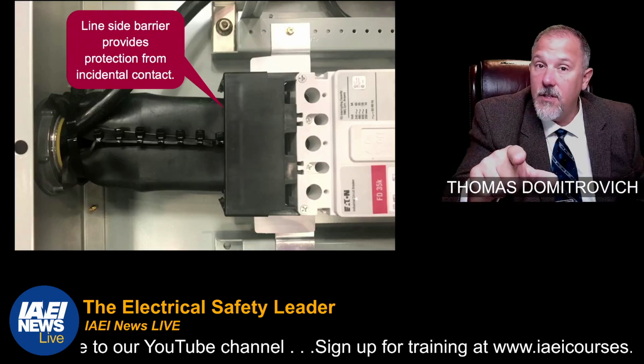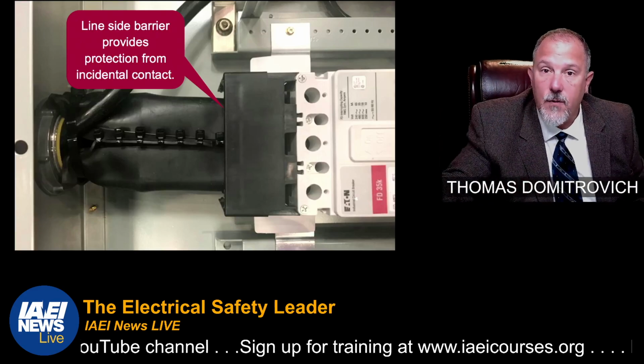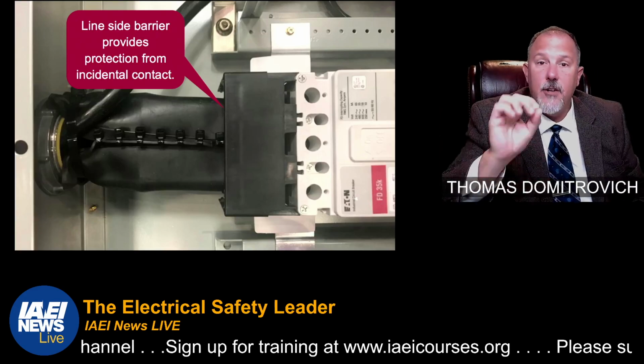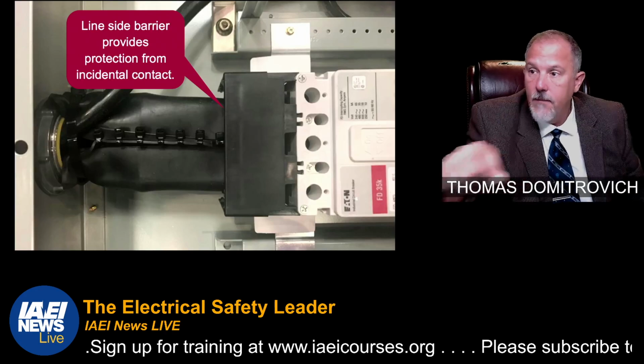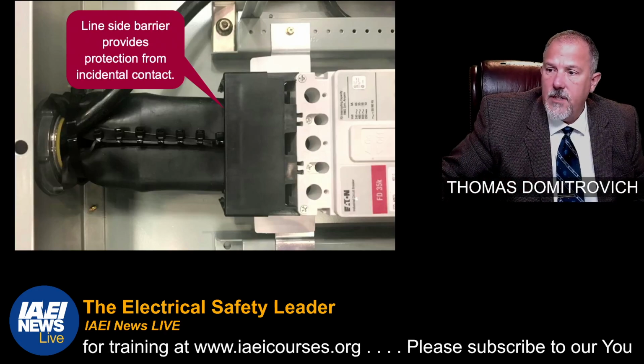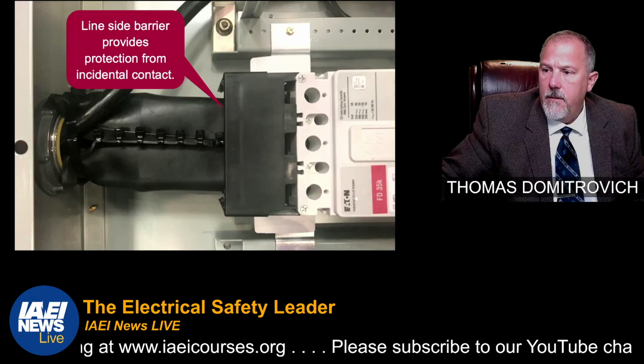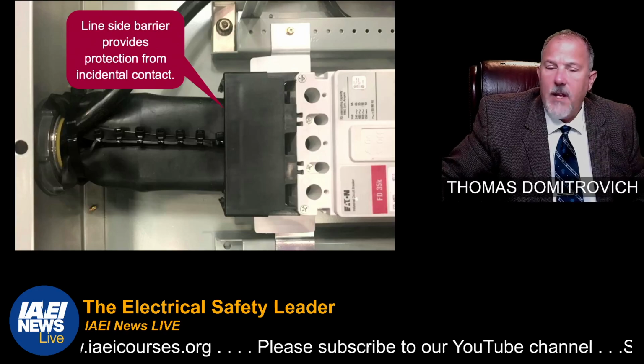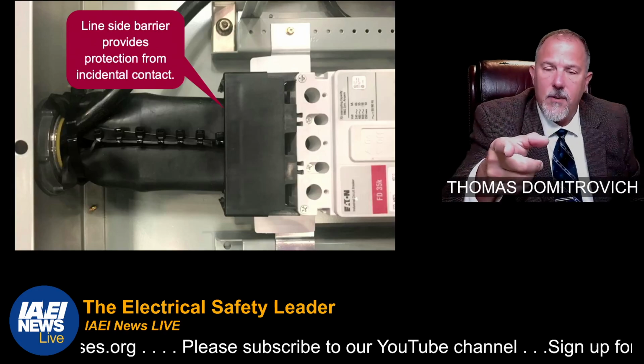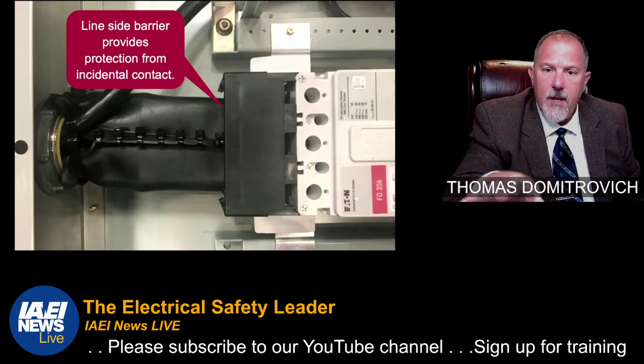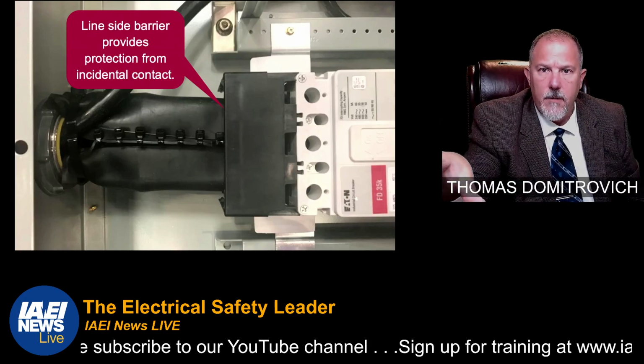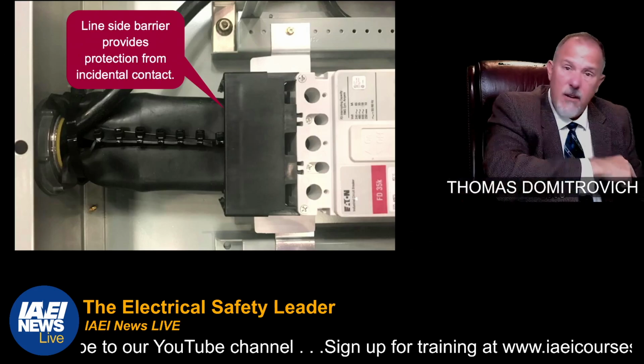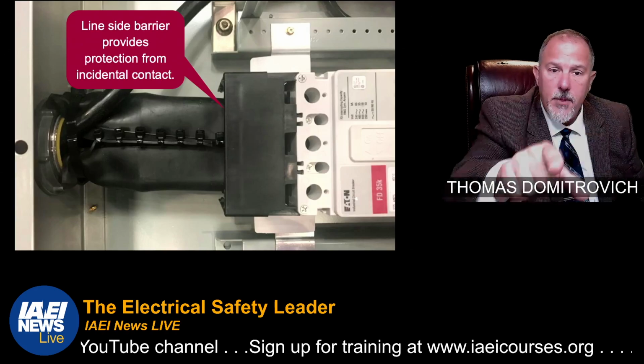If I can reduce the likelihood of you coming in contact with that, whether this panel is at the service or on the secondary of a transformer, because we made some changes in Article 215 for feeders. I believe it was 215.15. Check that out in the 2023 code cycle. If you have a panelboard on the secondary of a transformer, or a panelboard at the service equipment, you're going to have to put these barriers on it.